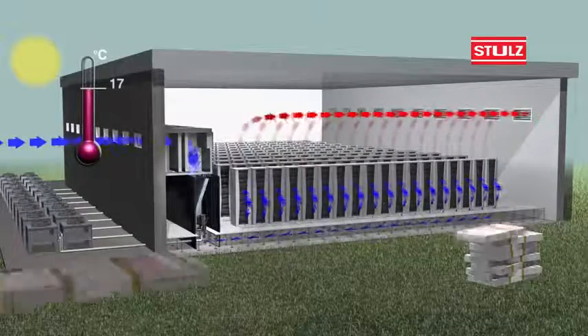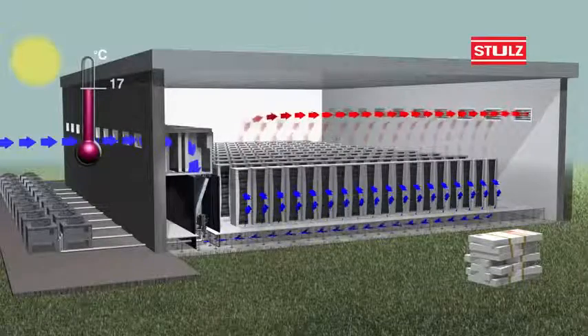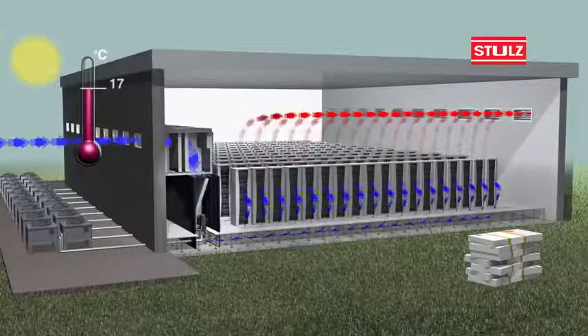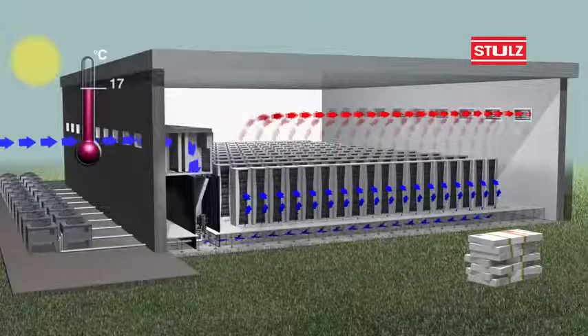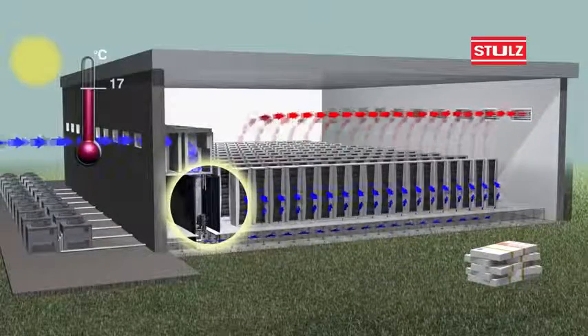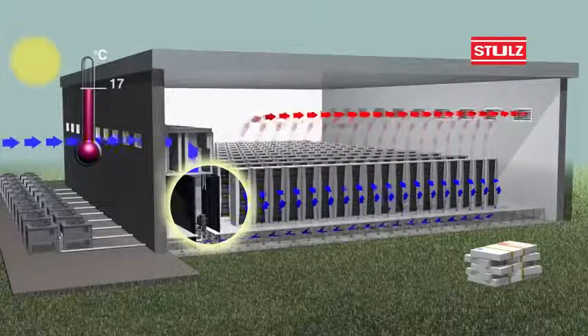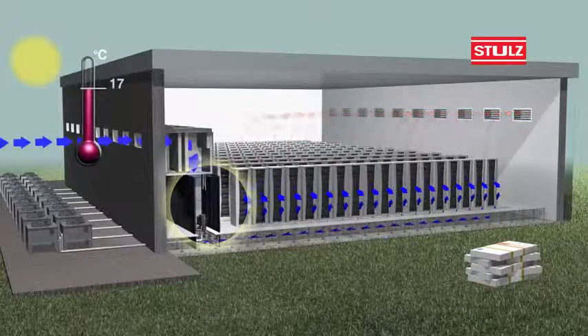When outside temperatures are below 18 degrees Celsius, our direct-free cooling uses 100% filtered outside air to cool the data centre, making compressor operation unnecessary. To make the system even more efficient, we developed and patented a heat exchanger that automatically folds back in this mode of operation, revealing a clear, open path through which the outside air can pass freely. Thus, no additional losses are incurred by heat exchangers.